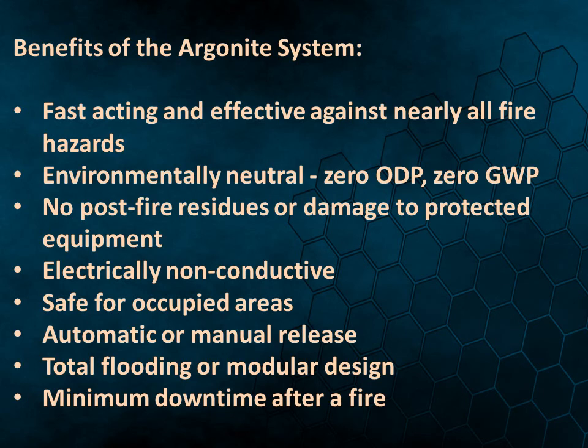Benefits of the Argonite System: It is fast acting and effective against nearly all fire hazards. It is environmentally neutral with 0 ODP and 0 GWP. There are no post-fire residues or damage to protected equipment. It is electrically non-conductive and safe for occupied areas. It supports automatic or manual release, total flooding or modular design, and results in minimum downtime after a fire.